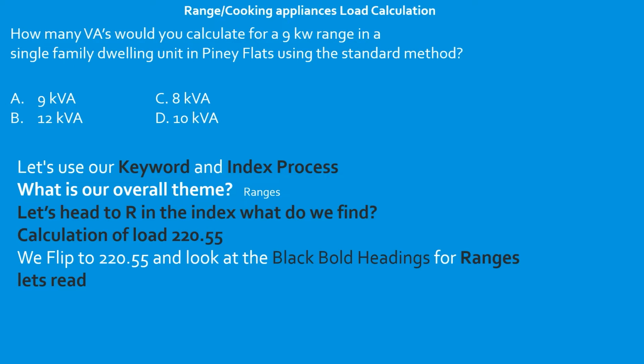Now you can go ahead and read that whole paragraph there. I'm going to give you the highlights. It lets us know that when we're dealing with ranges, wall-mounted ovens, counter-mounted cooking units, or similar things that are in excess of 1 3/4 kW, we're allowed to use Table 220.55. So we're going to head over to Table 220.55 and we're going to break it down. It's a very extensive table. In the next slide, we're going to go over it piece by piece.